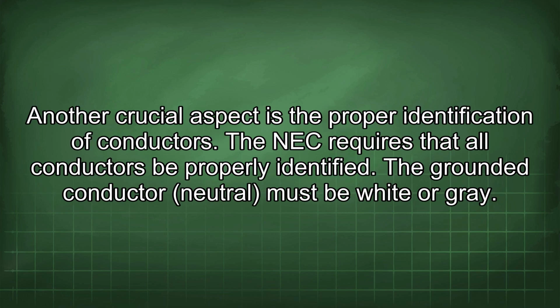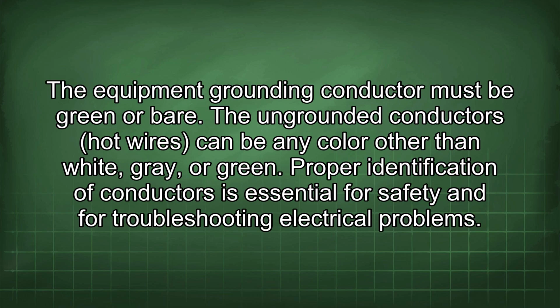Another crucial aspect is the proper identification of conductors. The NEC requires that all conductors be properly identified. The grounded conductor, neutral, must be white or grey. The equipment grounding conductor must be green or bare. The ungrounded conductors, hot wires, can be any color other than white, grey, or green. Proper identification of conductors is essential for safety and for troubleshooting electrical problems.